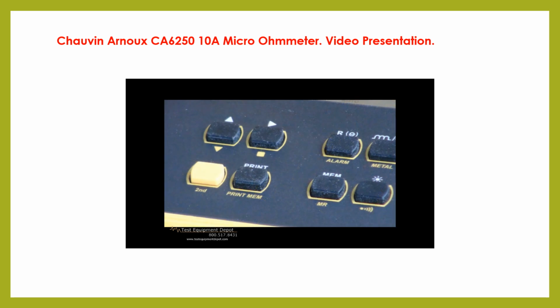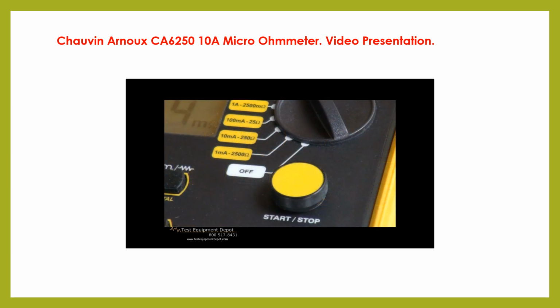That is why we have test currents available from 1 milliamp clear up to 10 amps. We're going to stress this bonding connection where 2 particular pieces of metal are touching, be it welded, or be it a cinch-down or torque-down lug and a bus bar, for example, in the case of power wiring.